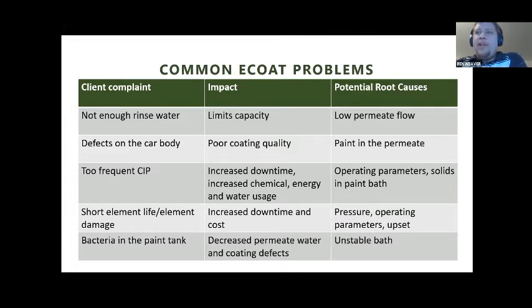And so we want to make sure that anything we can do to eliminate the potential for upsets is there. So if we have a VFD or soft start on the pump, that really prevents some of these upsets that cause element damage.